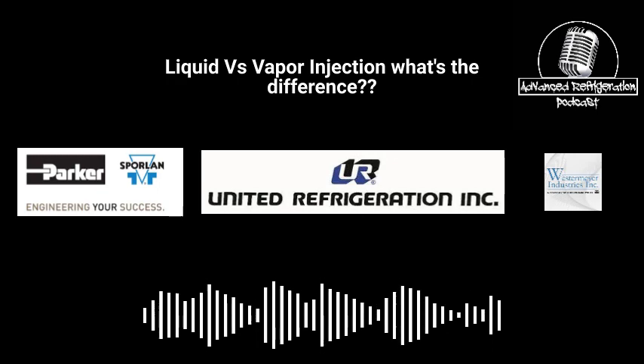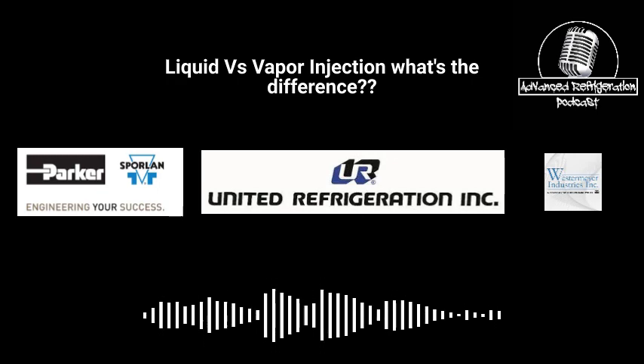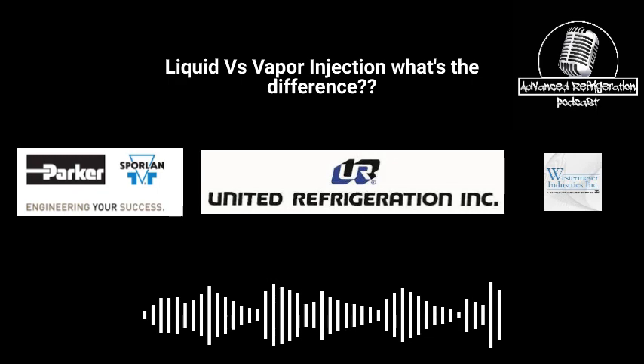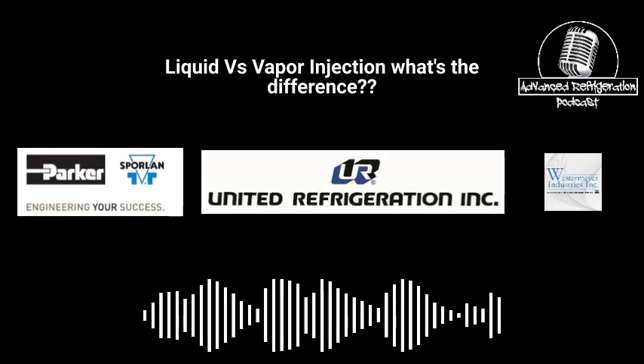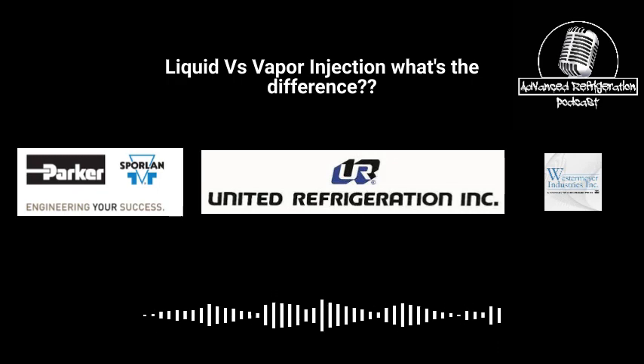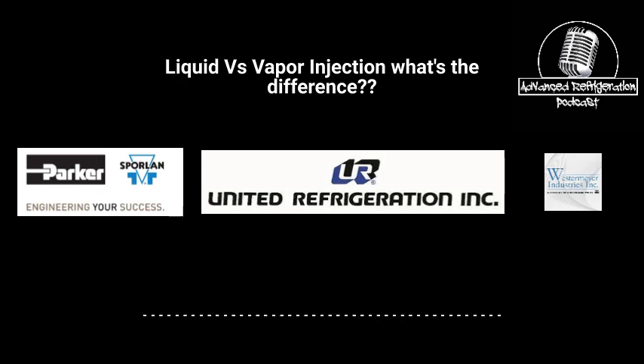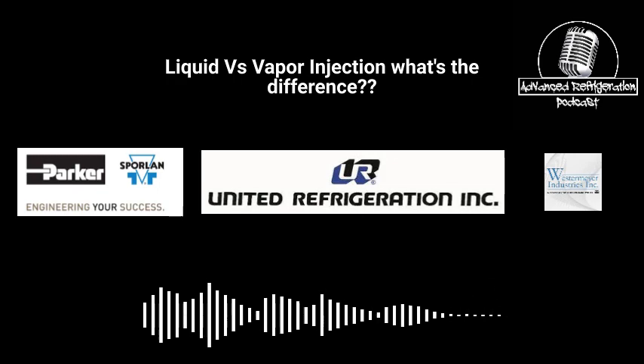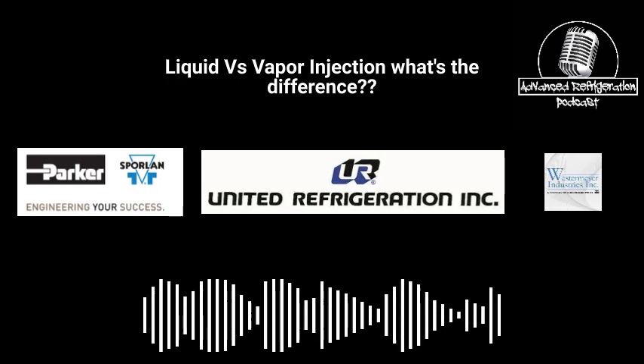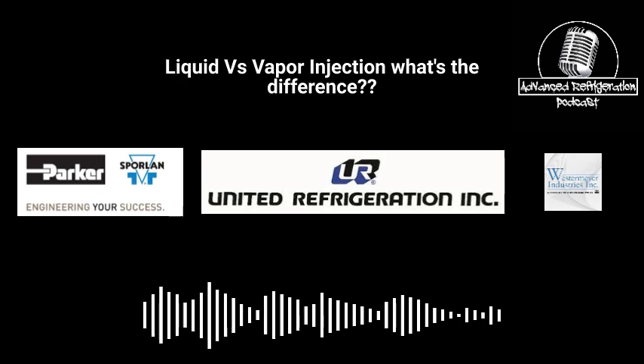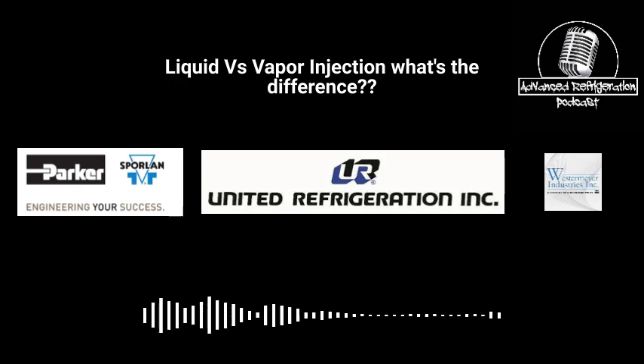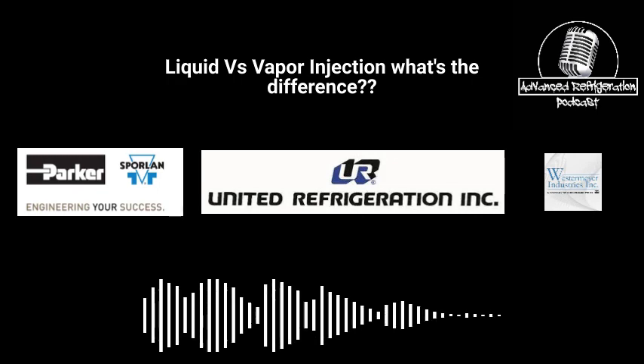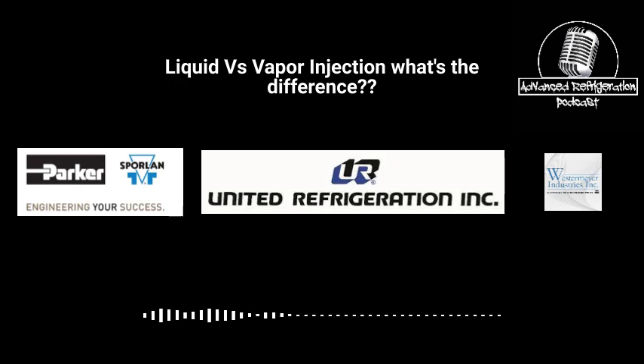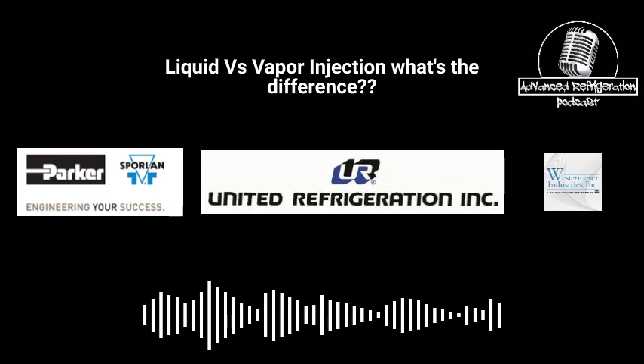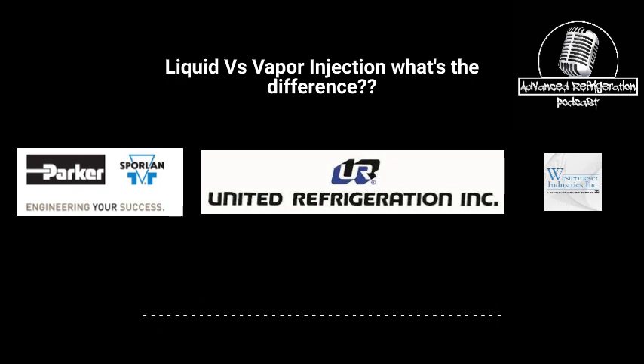I guarantee the subcooler has not worked at some point, or is down or not functioning properly, because that is your only form of cooling for those compressors with that high compression ratio. Correct. Also with the vapor injection, just to make you fully aware, not only do you need that vapor injection to make sure the paint doesn't bubble, but it's also going to keep your discharge line temperatures down, and keep your oil from turning brown. It'll make sure you're not adding so much heat that you're just cooking the thing.